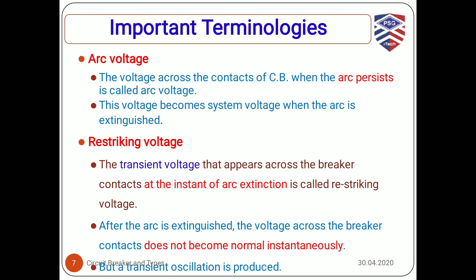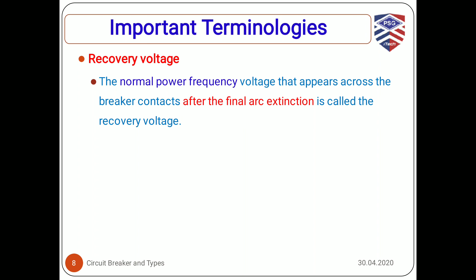Next, we will see the recovery voltage. It is the normal power frequency voltage. Previously, we have seen the restriking voltage, that is the transient voltage. The recovery voltage is a power frequency voltage that appears across the circuit breaker contacts after the final arc has been extinguished. So all these voltages we can see from this diagram.